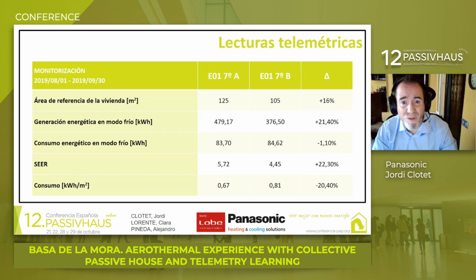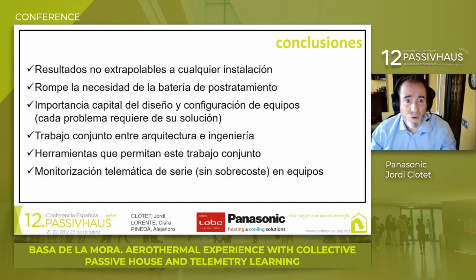But energy consumption was slightly lower in that apartment, and when we look at consumption per square metre, we can see that it's 20.4% lower in the apartments with underfloor cooling, 22% more efficient. So, without trying to extrapolate this example to all of Spain in conditions with climate similar to Zaragoza and the type of construction in Basa de la Mora, we can avoid the battery. In phase 2 it means less extraction costs, fewer material costs, better efficiency for final users.